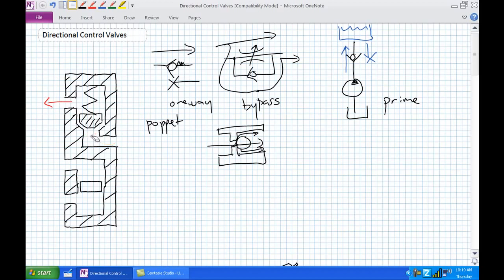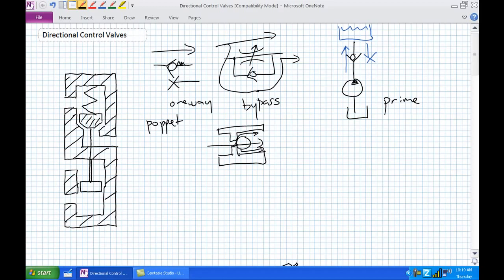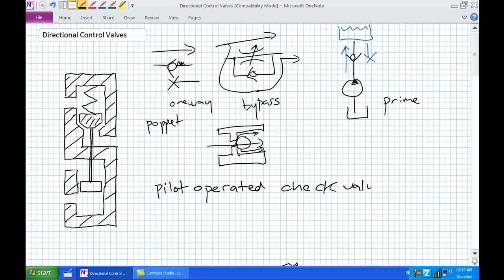If we modify this right angle check valve by adding a secondary chamber below it with a little piston that can move up and down, and connect them via a rod passing through, what we've got is a pilot-operated check valve. A pilot-operated check valve receives a pressure signal from somewhere else in the system.